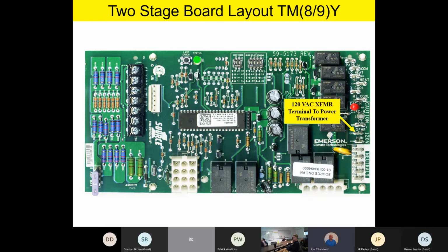Right below that, we have a 120-volt input called XFMR. That's for the primary side of the transformer, so that 120 volts will be fed to the transformer primary on that terminal. And then finally, we have a 120-volt humidifier terminal down below. If you want to run a humidifier, you'll have an isolated relay output off the board to give you 120-volt output anytime we have a heating call. So anytime there's a heating call or a W call on the board, we will output 120 volts on that HUM terminal to operate a humidifier if so desired.